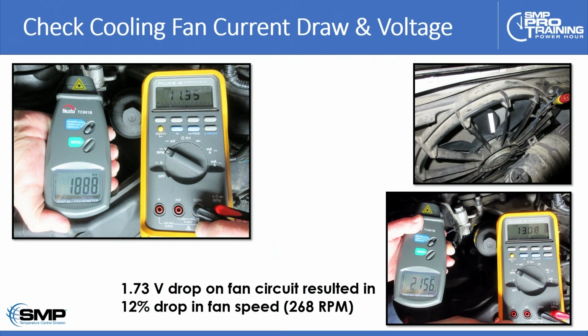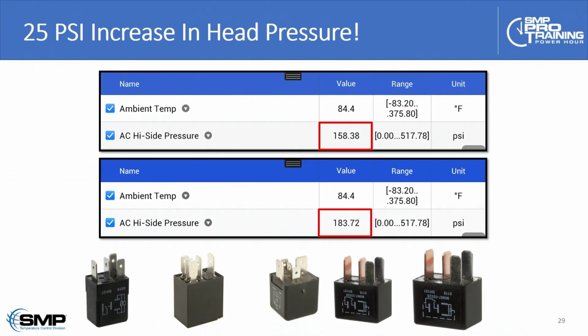And in the next slide, looking at our scan data, when we replaced the relay, the AC head pressure dropped about 25 psi. So again, airflow is very important and critical for air conditioning performance. Cannot overemphasize that enough.